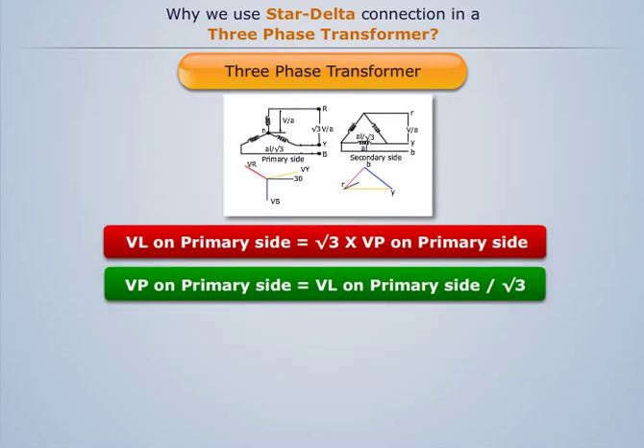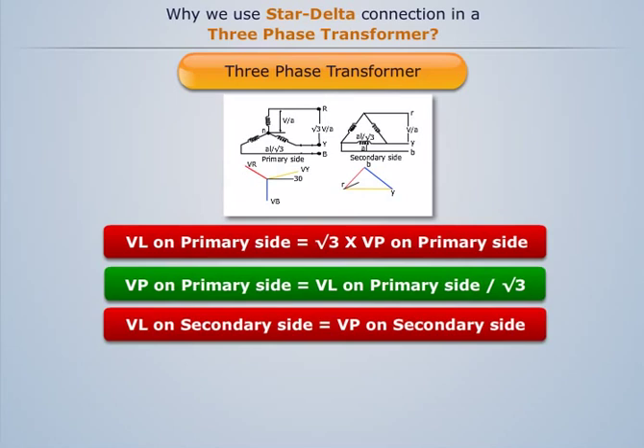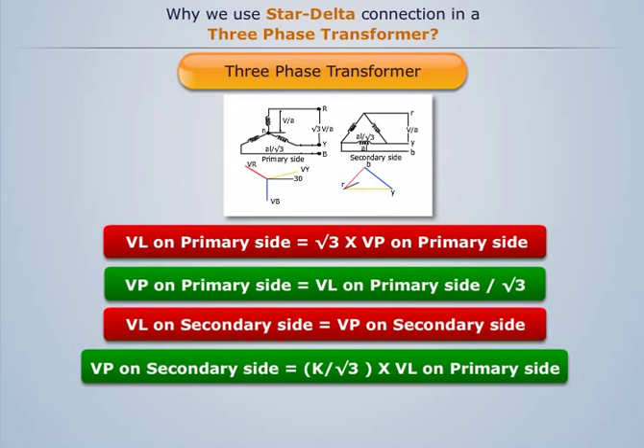And the secondary is delta connected. Line voltage on the secondary side is equal to phase voltage on the secondary side. Secondary phase voltage equals K divided by root 3 times line voltage on the primary side.